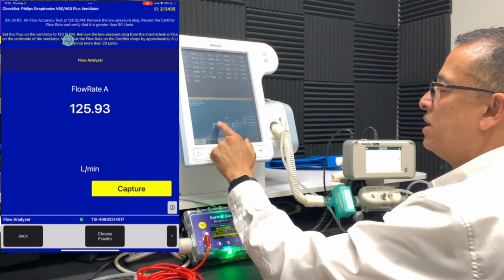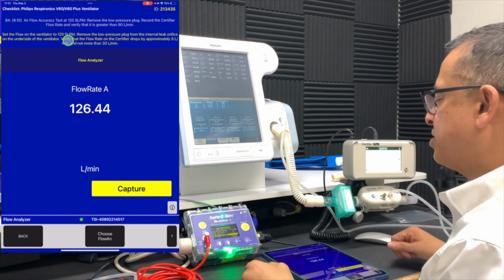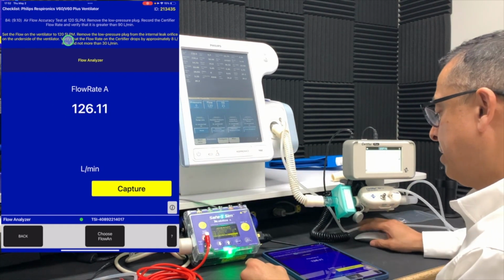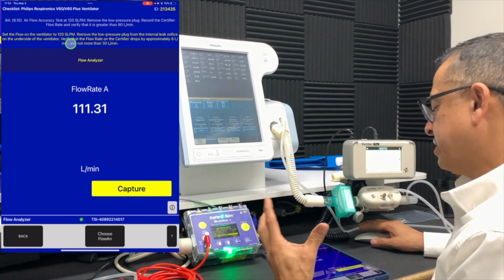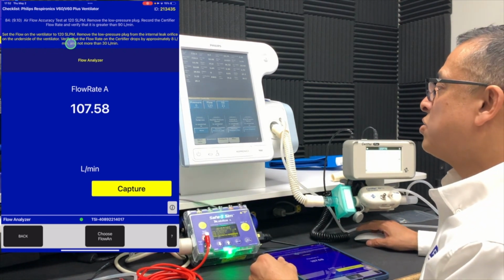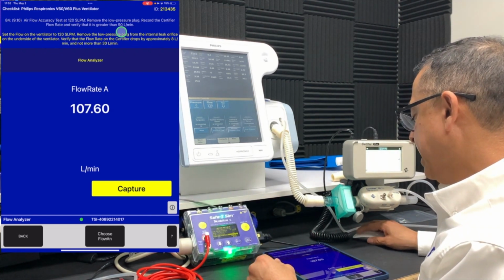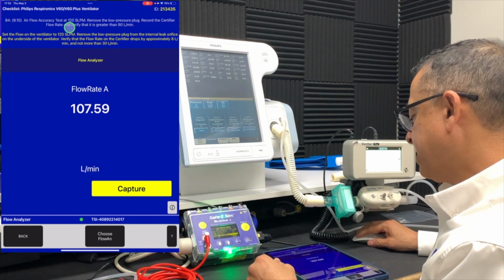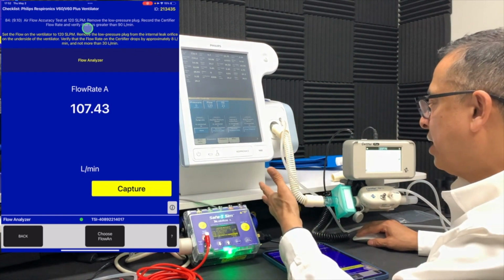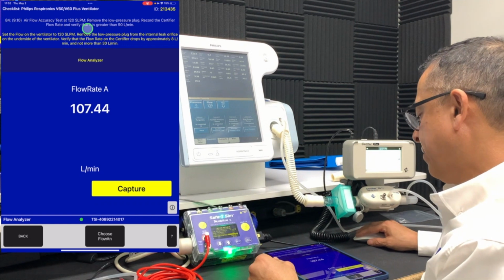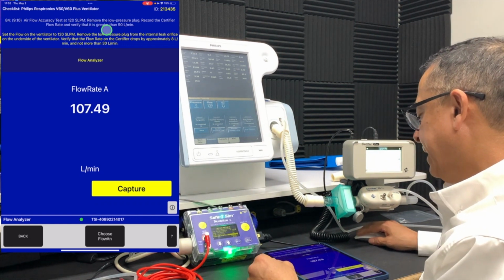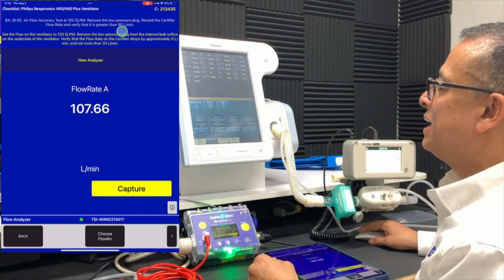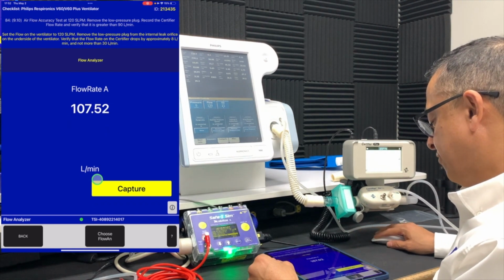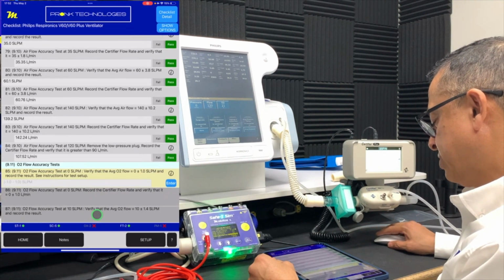You can see here why it's helpful to have the instructions here side by side to make sure we don't miss a step. The instructions here clearly tell us to set it for 120. So we'll confirm it. So at 120, I need to be over 90. So I've confirmed I've set it to 120. I've removed the plug, and I want to confirm that I'm seeing at least 90 liters per minute. And of course, we're measuring 107.66, well within specifications.